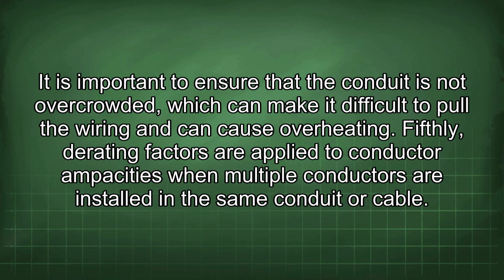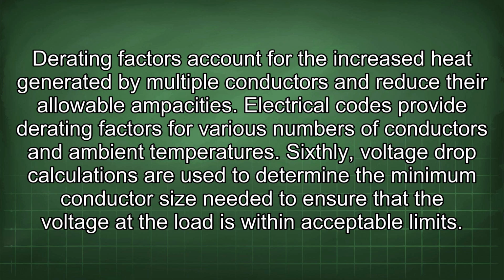and can cause overheating. Fifthly, derating factors are applied to conductor ampacities when multiple conductors are installed in the same conduit or cable. Derating factors account for the increased heat generated by multiple conductors and reduce their allowable ampacities. Electrical codes provide derating factors for various numbers of conductors and ambient temperatures.